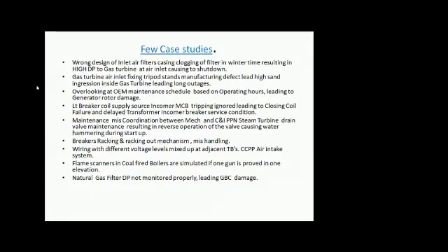And at the time when the steam turbine drain had to be opened at the beginning, the command was going from the control room, and the feedback was also coming, but the valve was physically, internally, closed. Because of that, water hammering happened. This is something people have to take care of, especially during actuator maintenance, and similar things can also happen during motor maintenance. And the other thing is breaker racking in, racking out. People also know that a few problems come because of not maintaining the breakers properly while racking in, racking out.